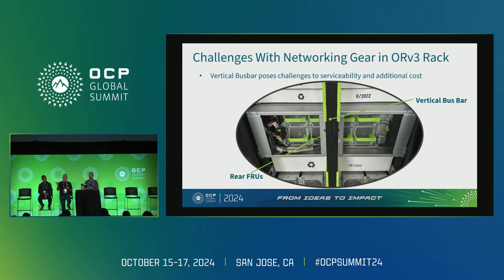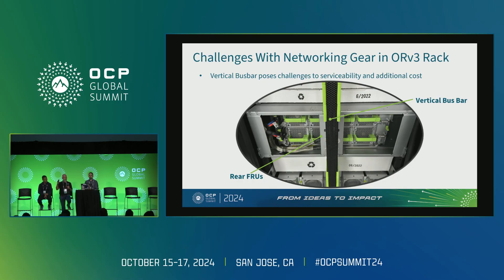With the bus bar, in ORV3 that bus bar just runs right down the back of the rack. If you look at any traditional network switch, you've got fans back there, you've got power supplies back there. On some of our switches, the entire main board pulls out the back — so that's a pretty big serviceability concern. In Grand Teton and other switches we had one or two switches in a rack, but now we're talking about a network rack with eight to nine switches. That serviceability impact on the bus bar really starts to become a concern for mass deployment. On compute, the entire system is designed accounting for that bus bar. Sure, we could have gone back and redesigned all of our network switches to account for it, but it's less engineering to just design a rack based on ORV3 that can better accommodate network.